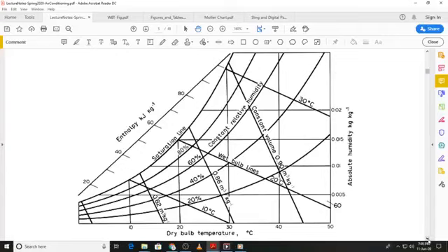Psychrometric charts number 1 to 4 are for the standard barometric pressure of 101.325 kPa, but for different temperature ranges. Psychrometric chart number 1 is for the normal temperature range from 0 to 50 degrees C, and it is the most commonly used psychrometric chart in the HVAC industry. The other three charts, 5, 6 and 7, are for different pressures.